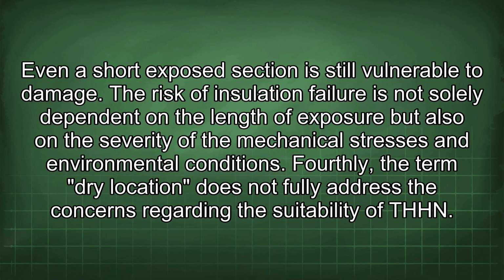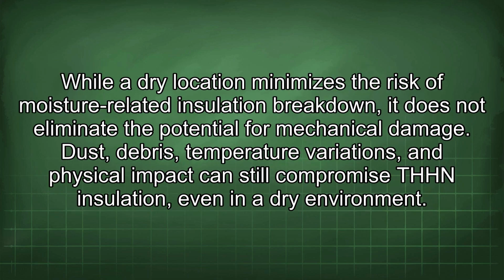The risk of insulation failure is not solely dependent on the length of exposure but also on the severity of the mechanical stresses and environmental conditions. Fourthly, the term dry location does not fully address the concerns regarding the suitability of THHN. While a dry location minimizes the risk of moisture-related insulation breakdown, it does not eliminate the potential for mechanical damage. Dust, debris, temperature variations, and physical impact can still compromise THHN insulation, even in a dry environment.